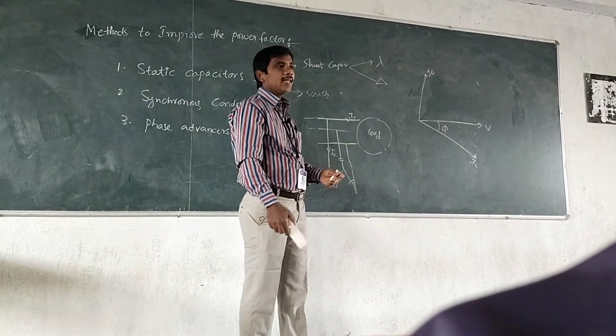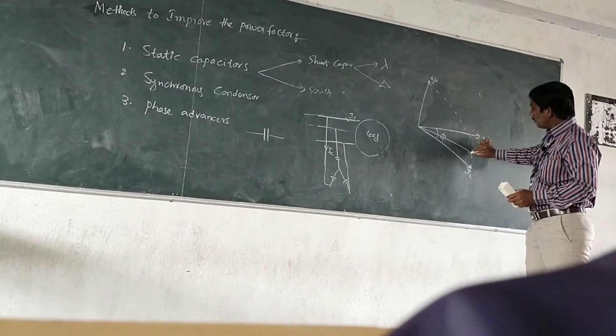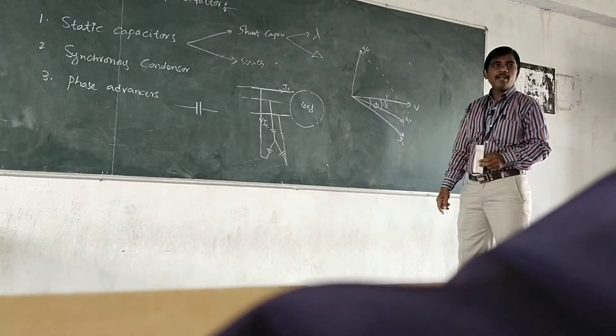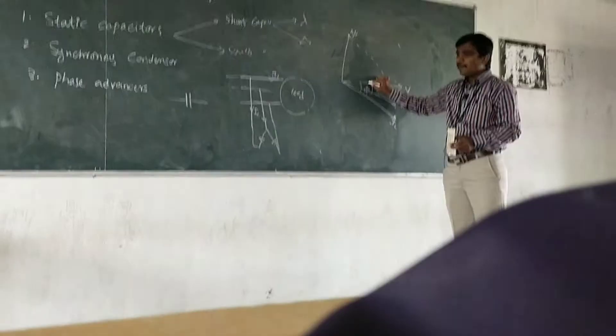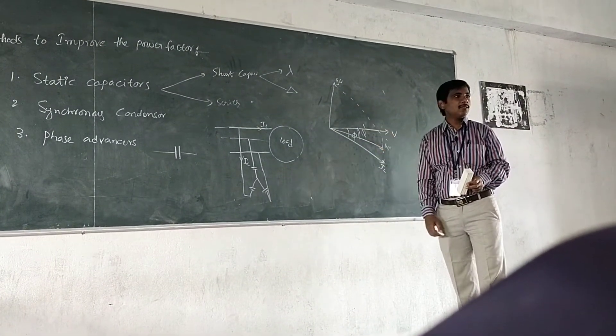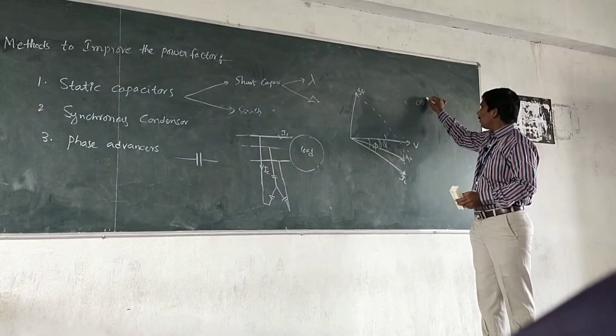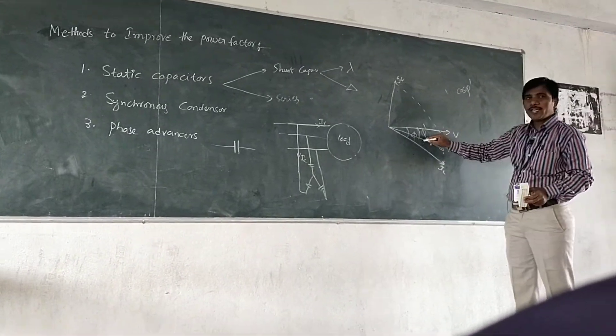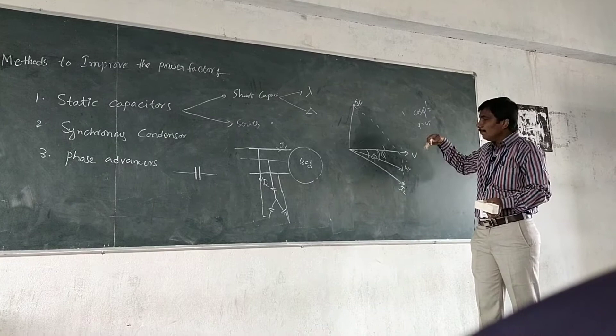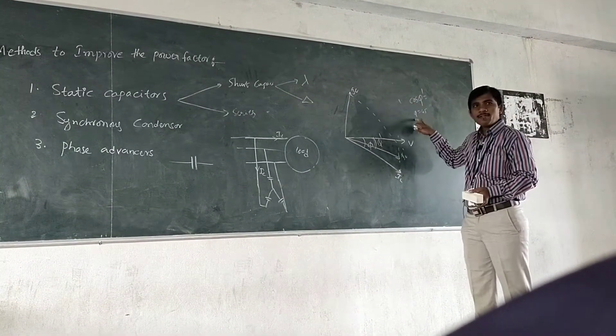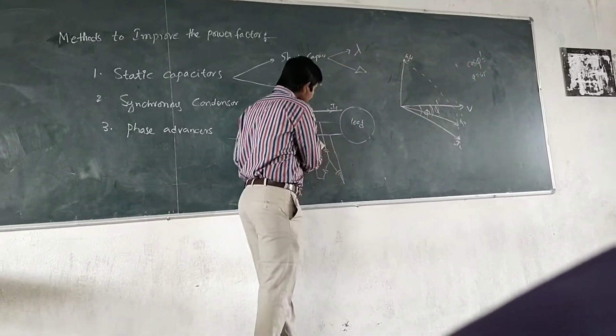Capacitor current always leads the supply voltage by 90 degrees. Now the resultant current IL dash has a new phase angle phi dash. This phi dash will be decreased due to the introduction of capacitors. If phi dash is decreased, then the power factor — cos phi dash — will improve. When phi decreases, the power factor improves. We can connect the capacitors in star and delta.